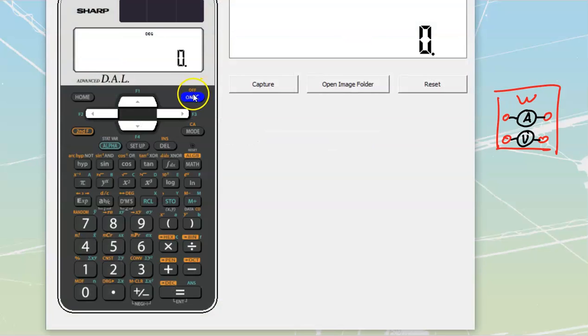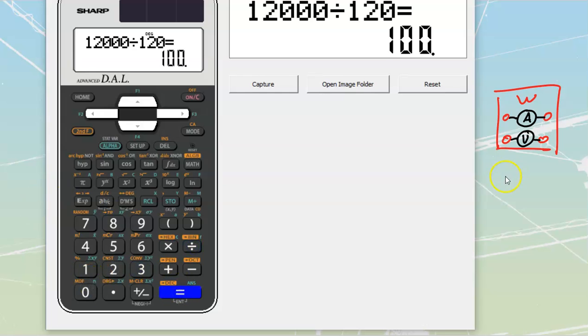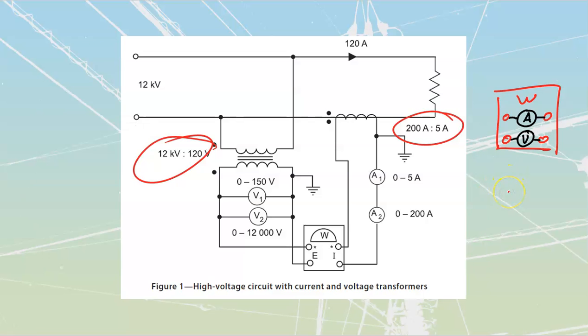If I were to pull those up on my calculator, 12,000 divided by 120 is a 100 to 1 voltage ratio that I have over here. So this is 100 to 1 that we have. We always write for a PT with a secondary of 120, so this would be the way that we would buy them. 12 kV to 120 talks about the actual voltage ratings, but the actual internal ratio itself is 100 to 1.